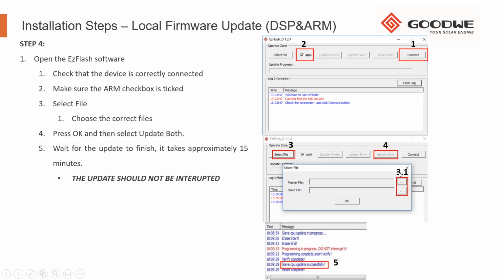So once we've selected our files, we press OK and we go to update both. You'll see it will run through. We'll see master update success, then it will go through and run slave. Should your slave fail and your master has gone through successfully, you can also just use update slave in your retry attempts. Like I say, sometimes it does fail if everything was selected correctly and there was some electromagnetic interference. You can just switch the inverter off again, leave it for 15 minutes or so, make sure the USB is out, nothing's powered on. Reboot your laptop as well for good measure, power on the device, plug in the USB again, and then try again. Normally that then allows us to update it successfully.